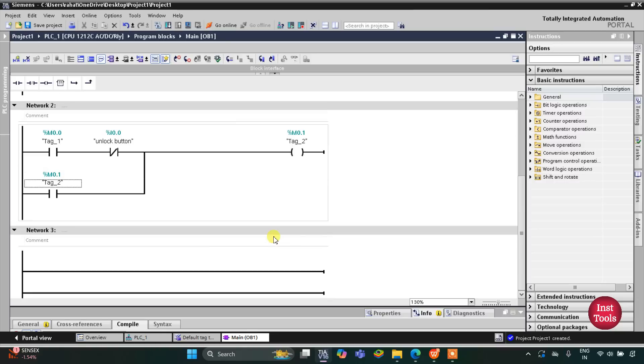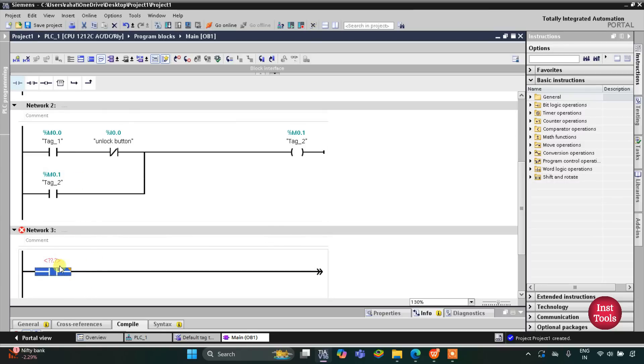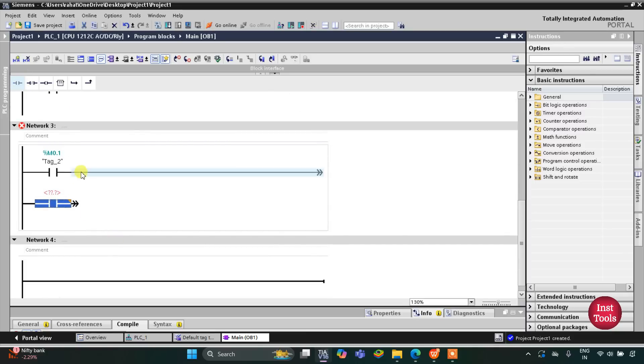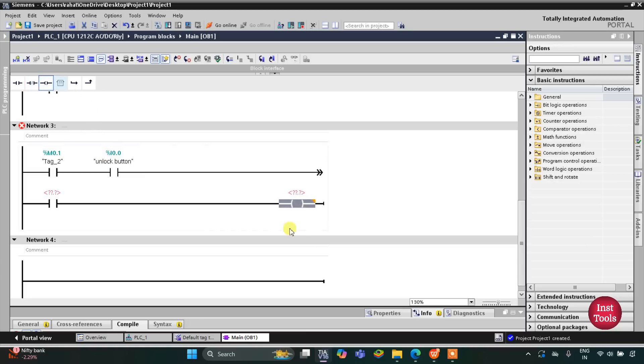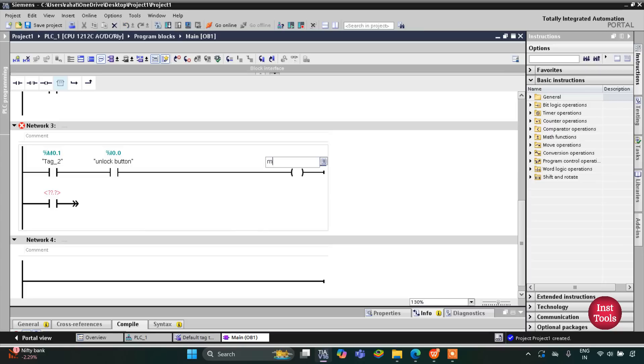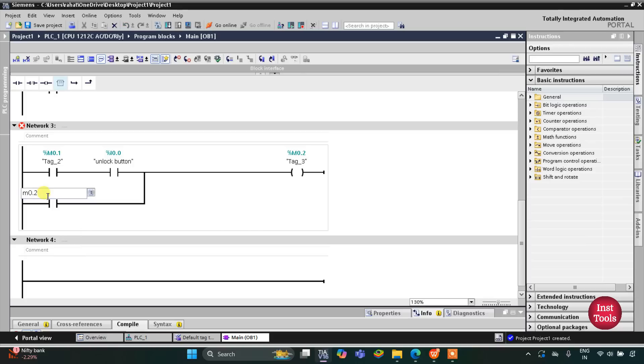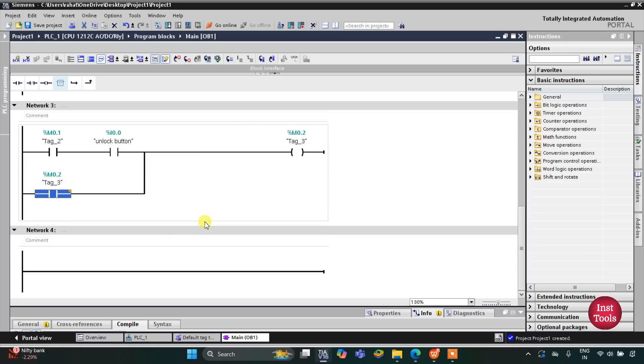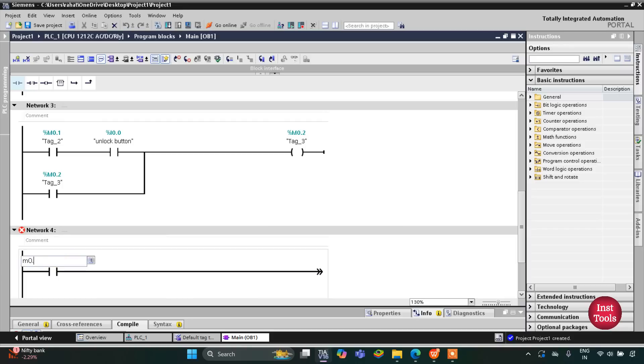When M0.1 is true — meaning the button has been released — and then the unlock button is pressed again, another memory bit M0.2 gets true. We latch it, connecting it like this. M0.2 stores the data that the unlock button is being pressed a second time.